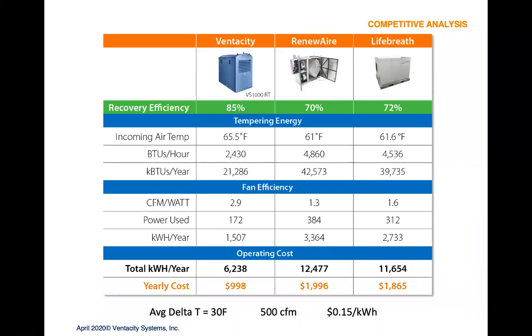So what you're looking at here is using about half as much energy when you've got very high efficiency heat recovery to provide that ventilation for a year into that classroom or school or office or building. Again, I'm just running 24/7, so we can play all we want with the model, but this gives you an indicator of what the difference is. It's about half as much energy and half as much cost to provide that ventilation. So really an important factor.